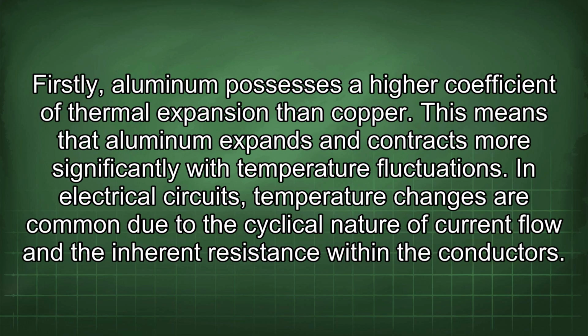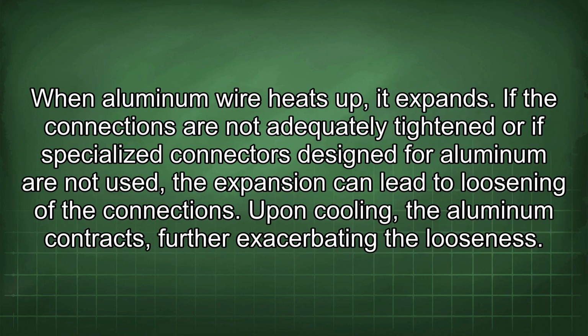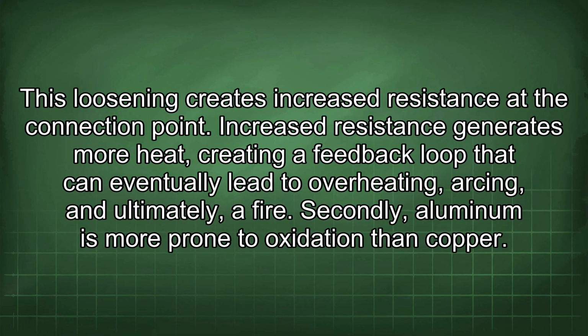Firstly, aluminum possesses a higher coefficient of thermal expansion than copper. This means that aluminum expands and contracts more significantly with temperature fluctuations. In electrical circuits, temperature changes are common due to the cyclical nature of current flow and the inherent resistance within the conductors. When aluminum wire heats up, it expands. If the connections are not adequately tightened or if specialized connectors designed for aluminum are not used, the expansion can lead to loosening of the connections. Upon cooling, the aluminum contracts, further exacerbating the looseness. This loosening creates increased resistance at the connection point. Increased resistance generates more heat, creating a feedback loop that can eventually lead to overheating, arcing, and ultimately a fire.